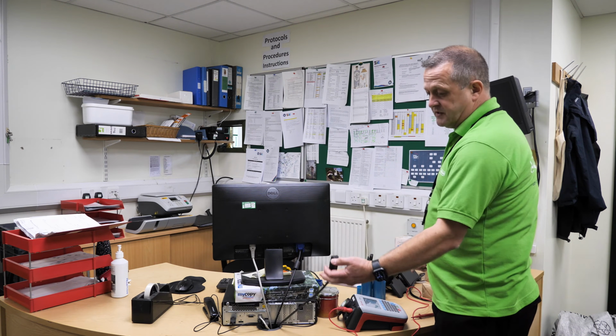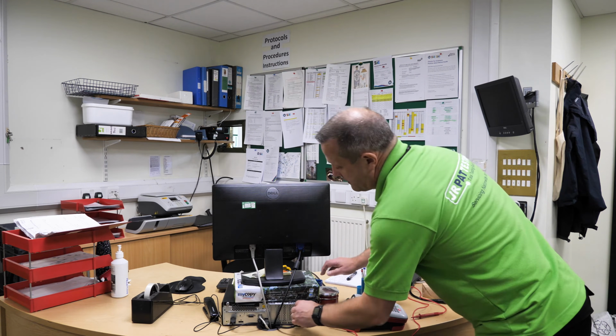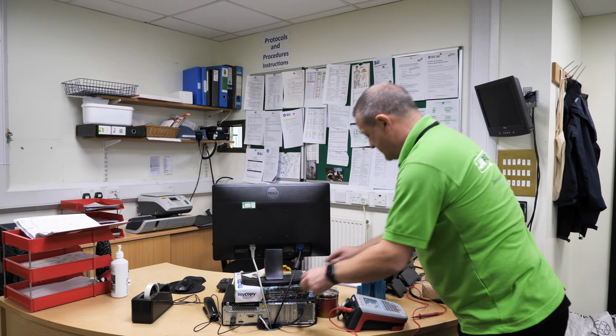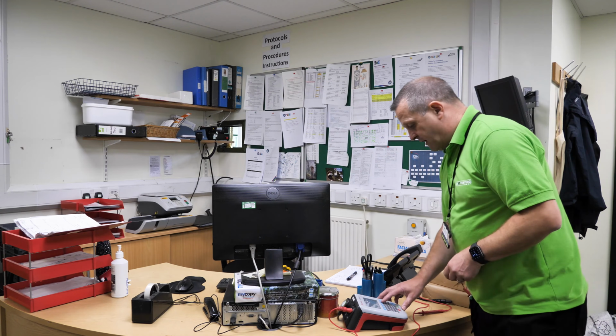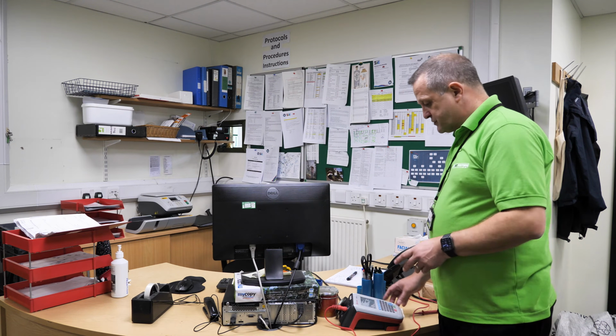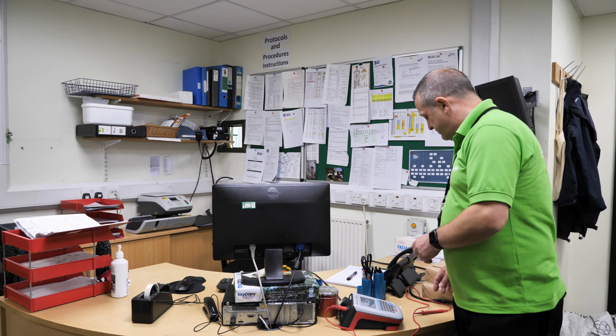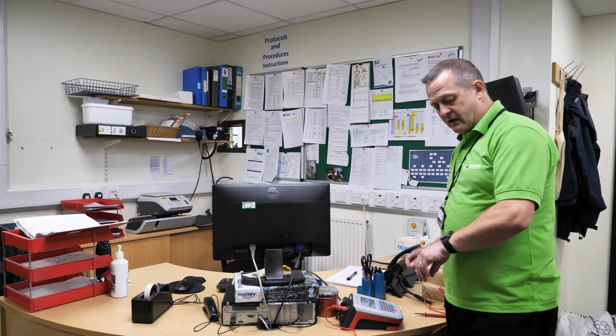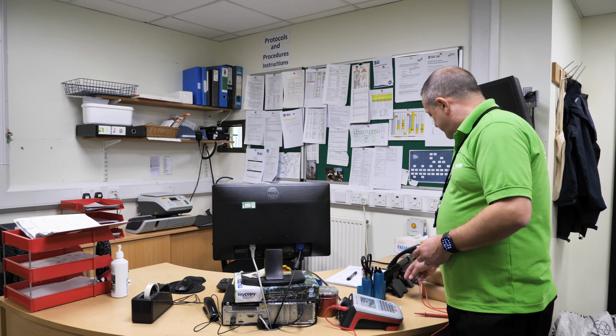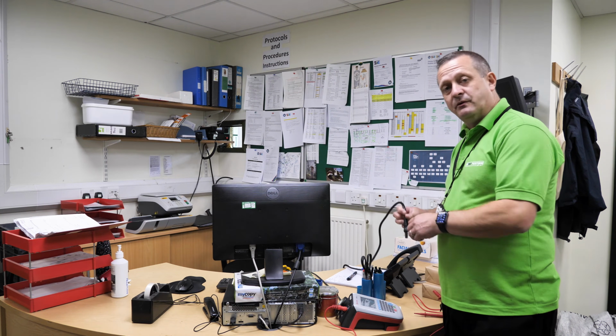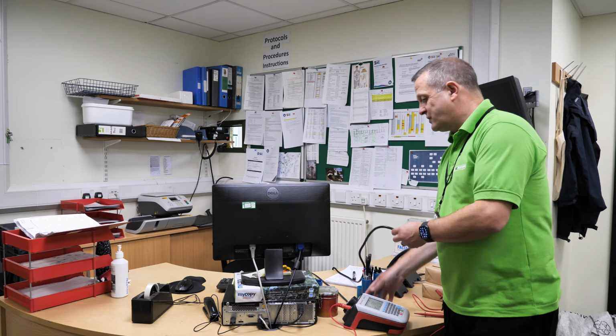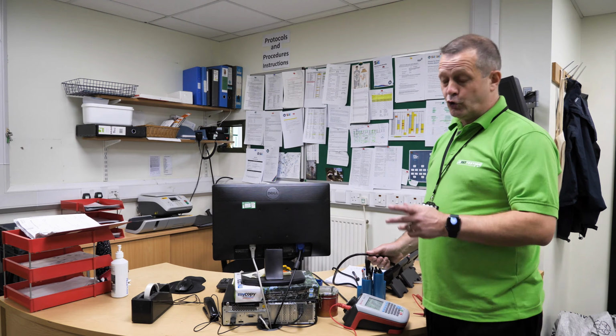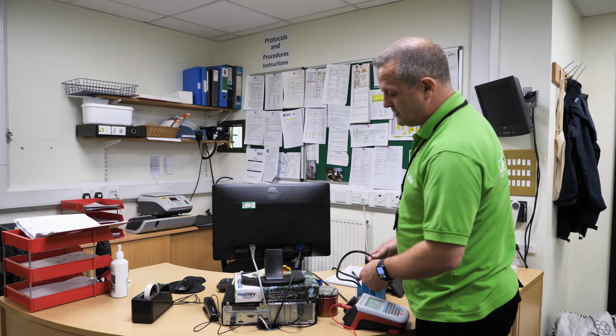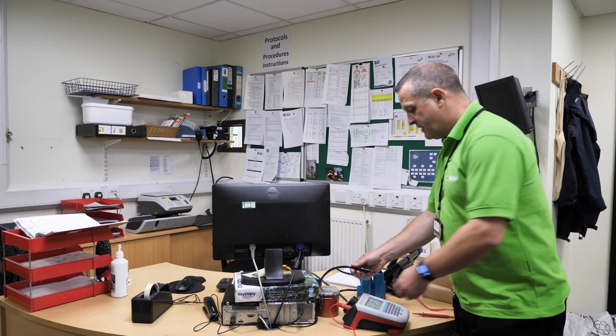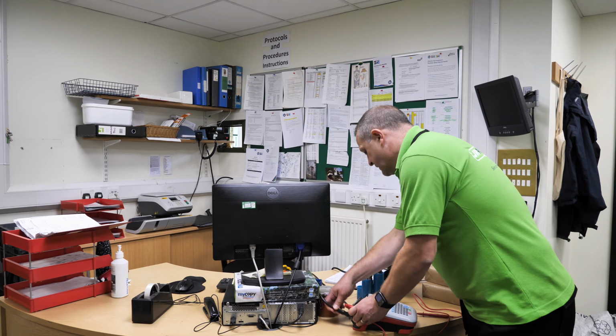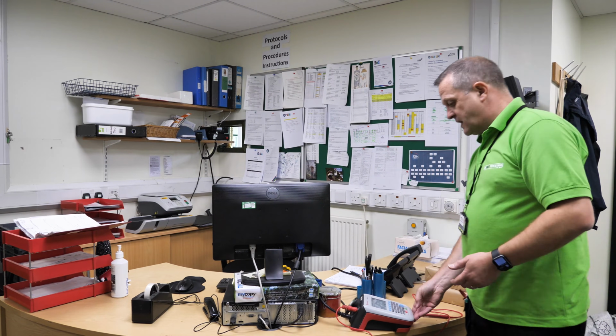We'll then remove the IEC part of the lead, put that back into the base station, and this time, because we are dealing with computer equipment, we need to reduce the voltage that we are using. Normally on the PAT testing machines that goes through at 500 volts, but because we're talking about IT equipment, that amount of voltage could cause some damage to the internal components, so we need to reduce that down to 250 volts, and we do that by doing a 250 volt test.